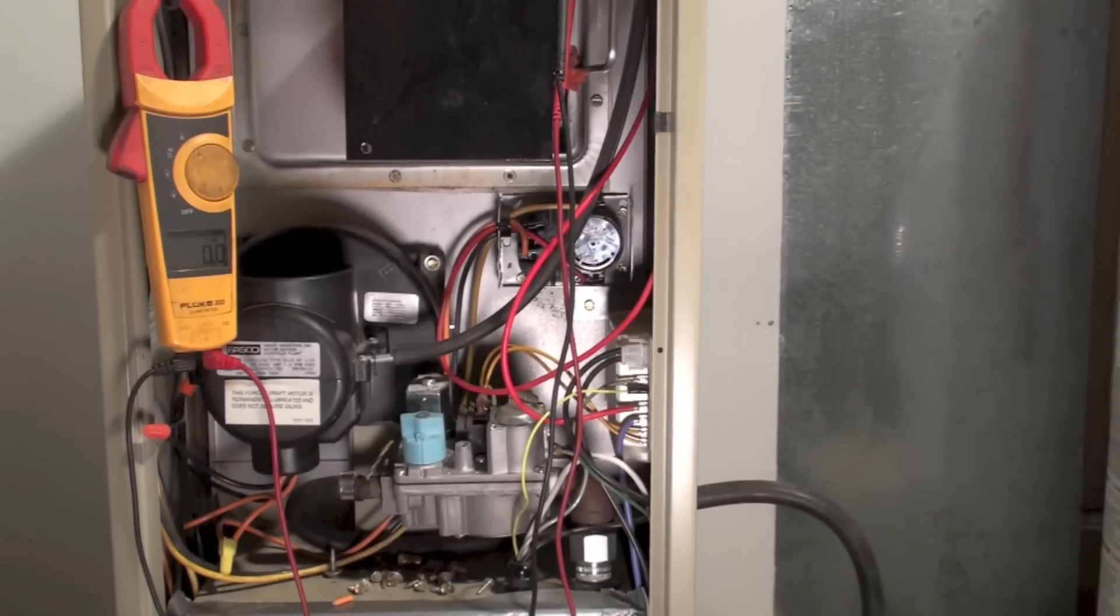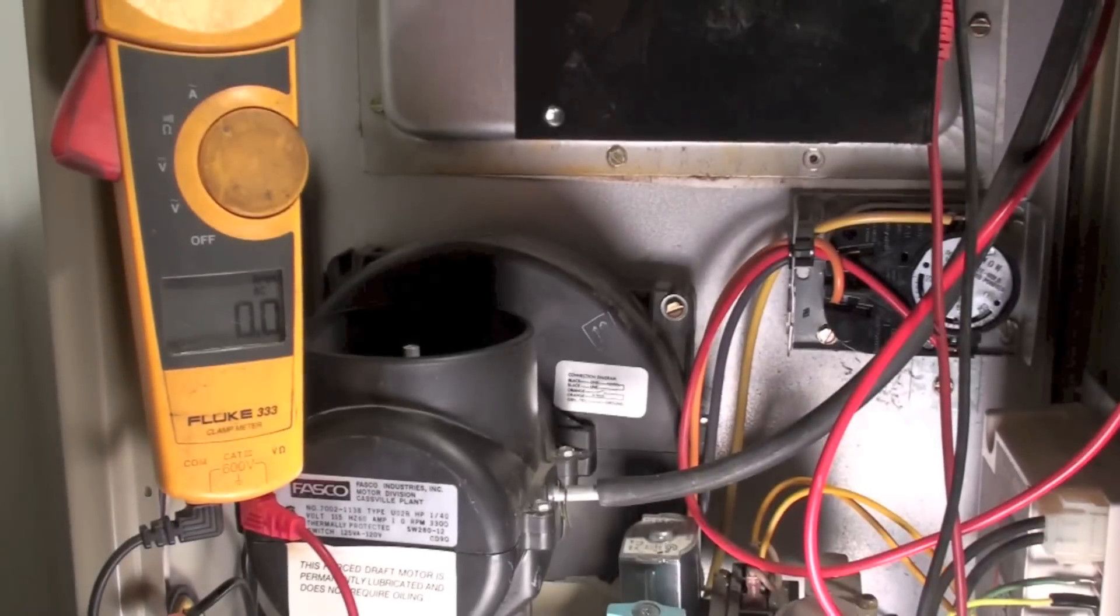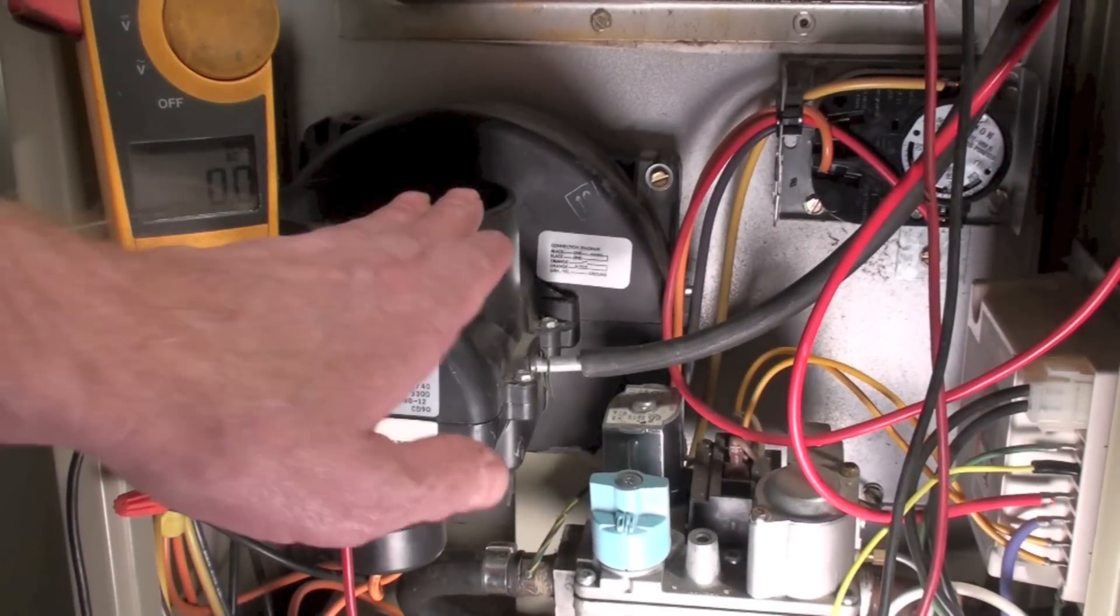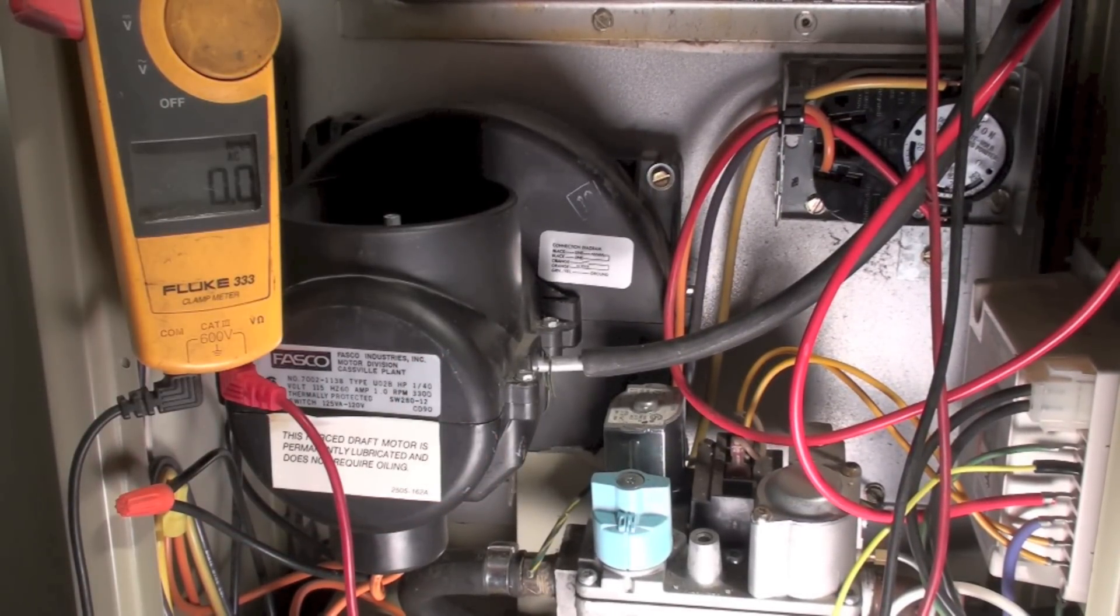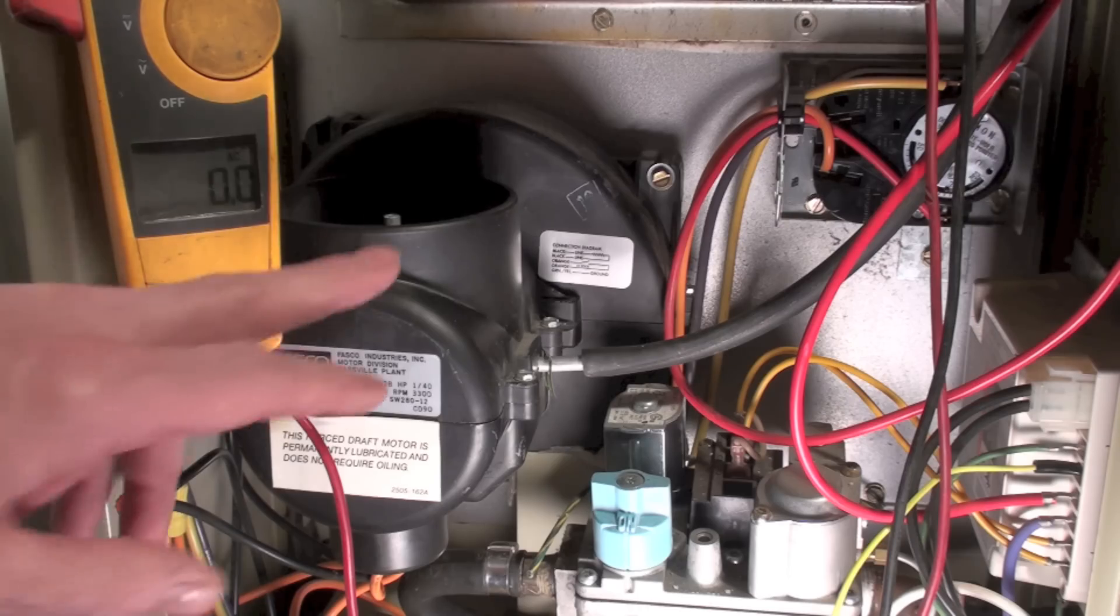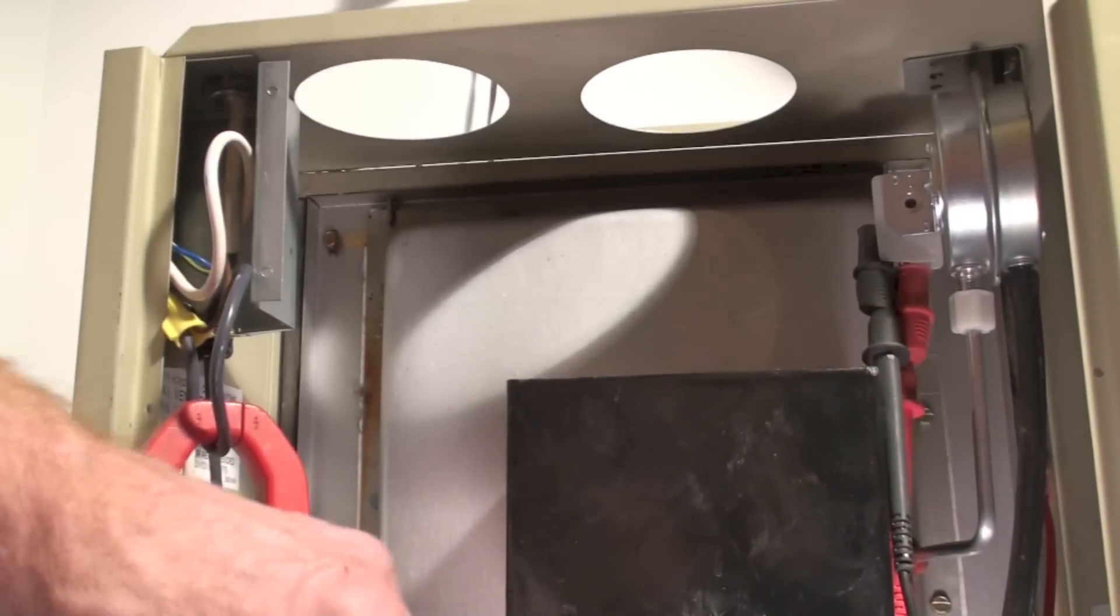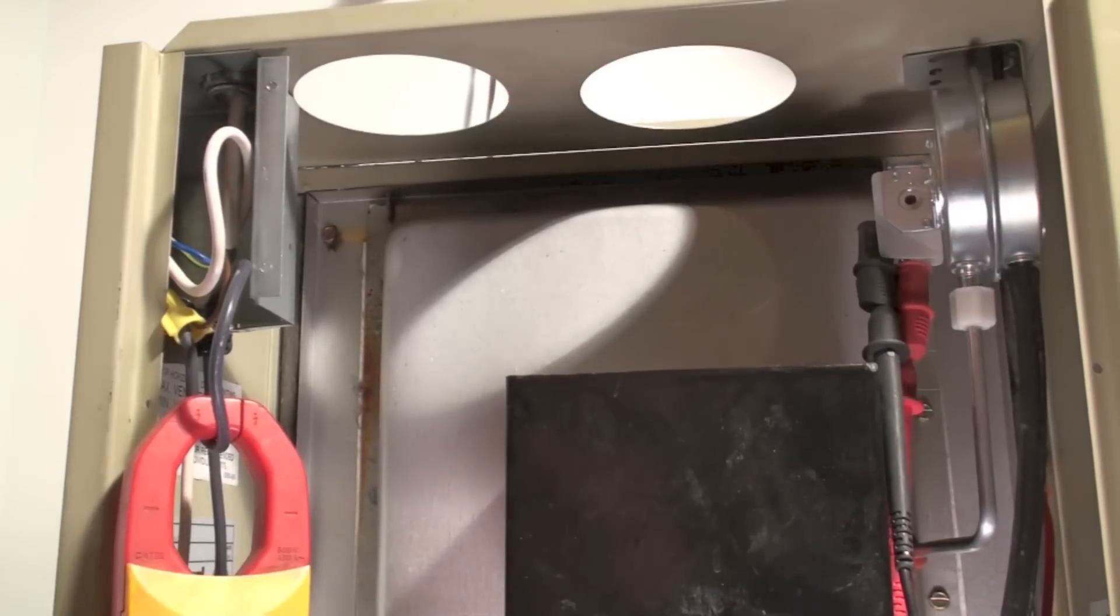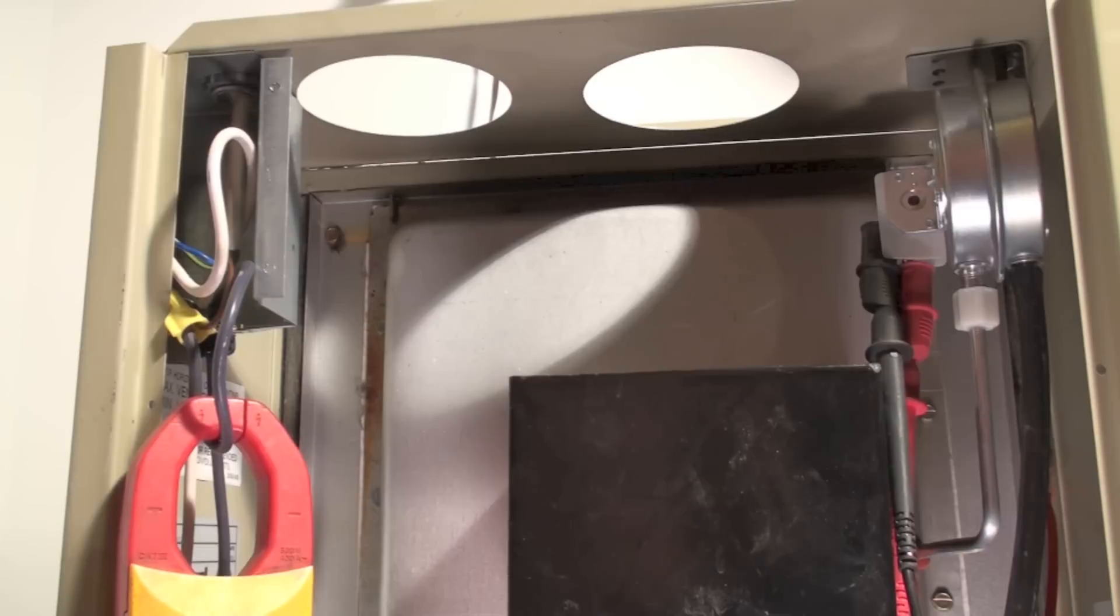It's supposed to shut off if the combustion air inlet, which is right in front of you there, which has a sensing tube right there in the middle of that pipe, goes up to the pressure switch right there and senses if the combustion air inlet is blocked.